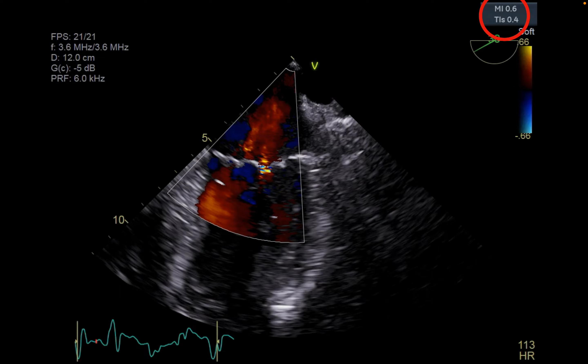So let's continue on with the thermal index. As you see here, thermal index can be thought of as the current acoustic power output over the power required to raise the temperature by 1 degree Celsius. So broadly speaking, if the TI is 2, then it means that your surrounding tissues will be warmed by about 2 degrees Celsius. It doesn't really mean that, but you can think of it that way. So the higher the number, the more heat will be produced. And as we discussed earlier, this is due to absorption and attenuation, and it is a property of all ultrasound systems. There are 3 different thermal indices that we distinguish between.